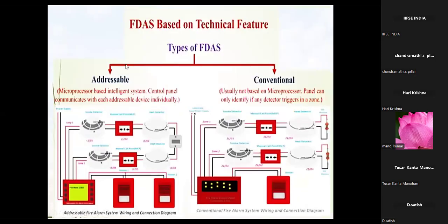Based on technical features, FDAS systems have two types. One is addressable, which is a microprocessor-based intelligent system with a control panel that communicates with each addressable device individually. That means if you have maybe 10, 15, or hundreds of devices, this microprocessor has the ability to communicate individually with each alarm or detection system.